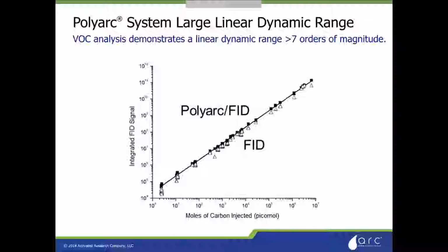This is an important curve that I want to point out. If you look at moles of carbon injected, so this was actually done in an on-column system where the analytes were injected right onto the column. And so you can look at the number of moles of carbon that were injected versus the FID signal. And these data points are from several injections of different concentrations and different oxygenates. And you can see they all lie on the same curve because they're all being converted to methane. So what we're measuring here is conversion to methane and just measuring the FID signal of methane. And this is important because this is your universal calibration curve right here. And you can see with the FID there's some variability. This is a log-log plot, so those are actually pretty big changes.